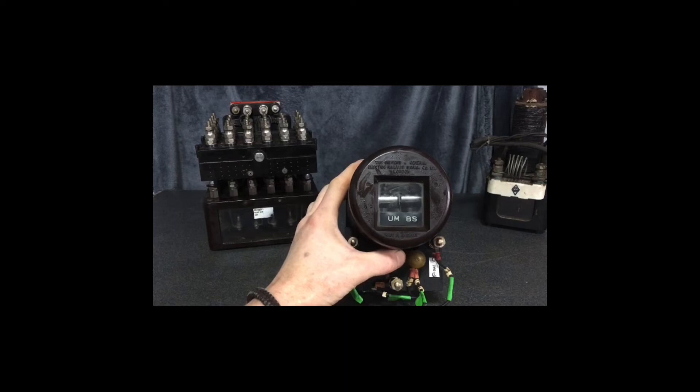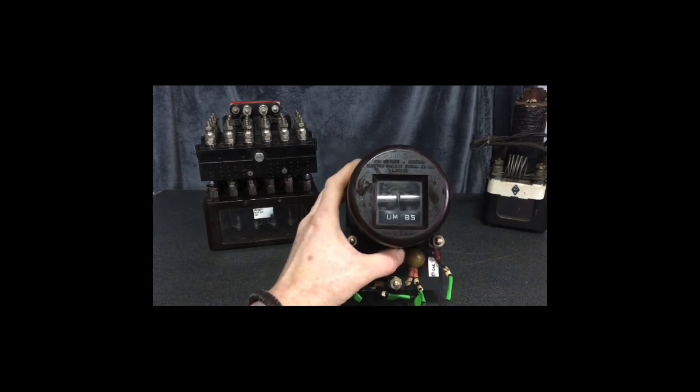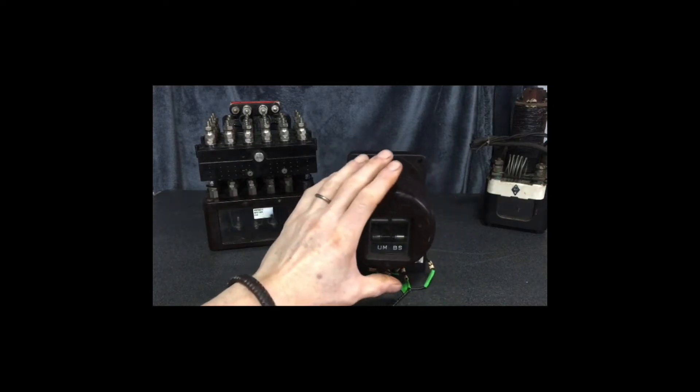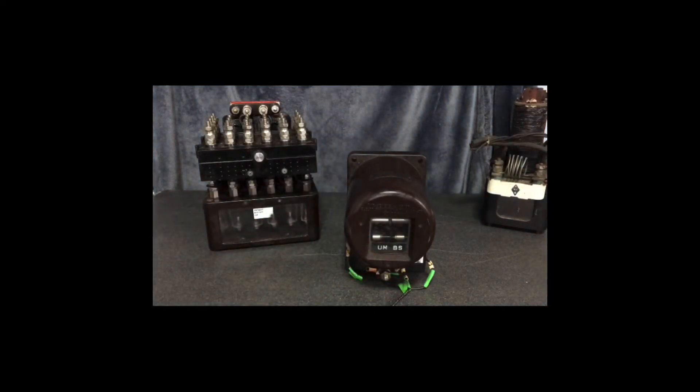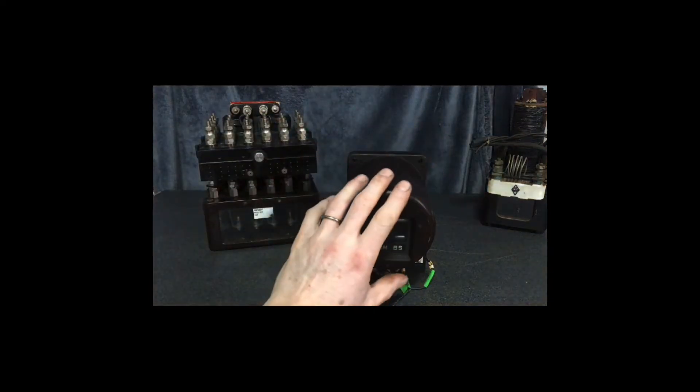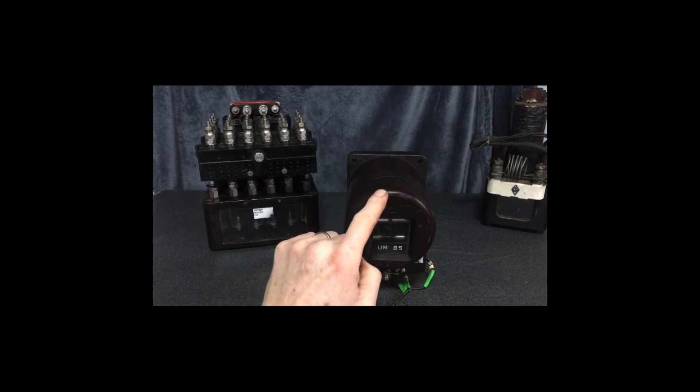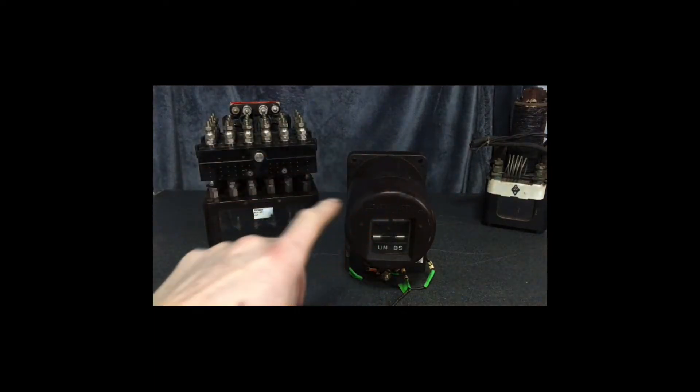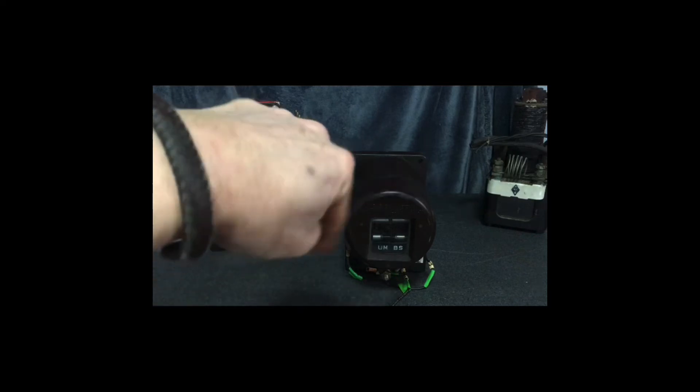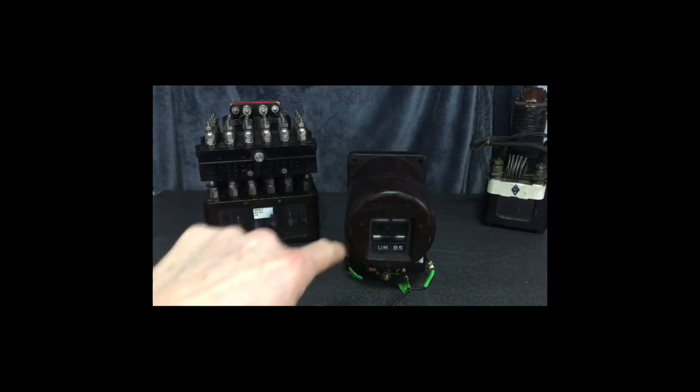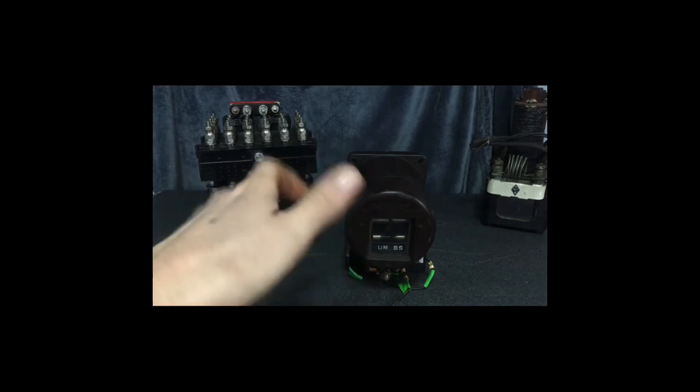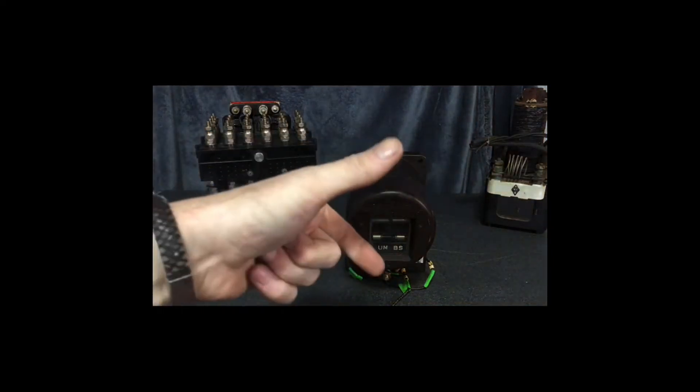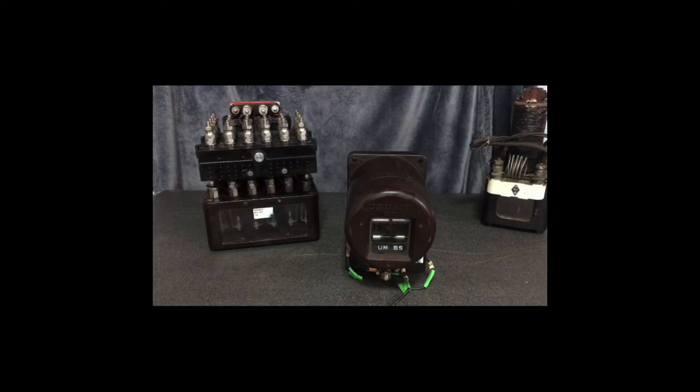That's why we use these. There are two contact versions of these in a nice square case. These tend to be used for block proving and stuff. If you have the two contact version of these in the square cases, they tend to be used for signal repeating. So in a contact box with a signal, you will switch round the contacts there. That will drive the relay and then it will give a double polarity output back to the signal box. So it will switch the positive and negative lines back on our polarity change circuits back to the signal box.